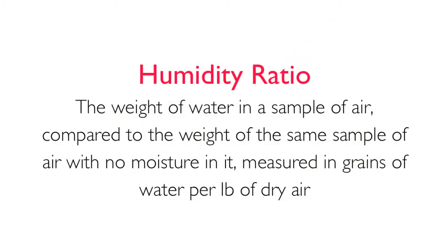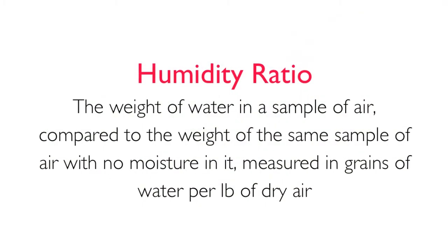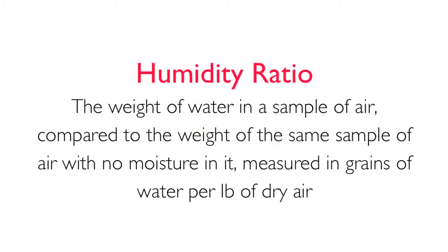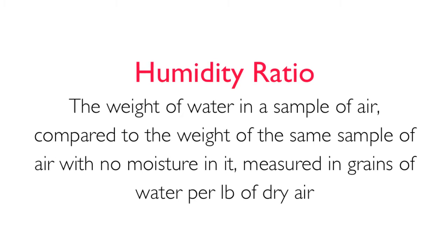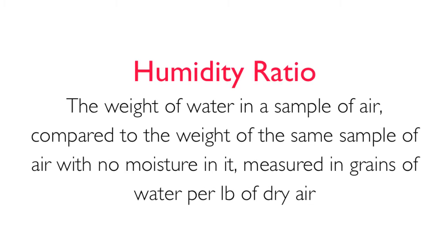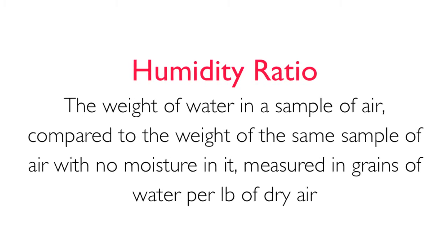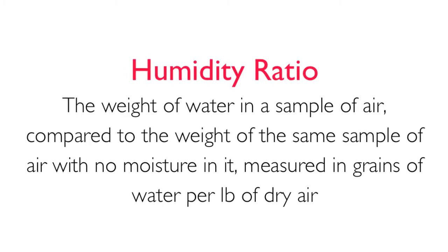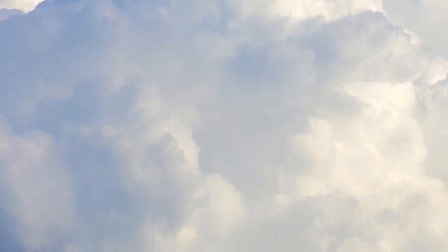Humidity ratio is the weight of water in a sample of air compared to the weight of the same sample of air with no moisture in it, measured in grains of water per pound of dry air. For example, at 70 degrees Fahrenheit with 30% relative humidity, the humidity ratio is 34 grains of water vapor per pound of dry air.